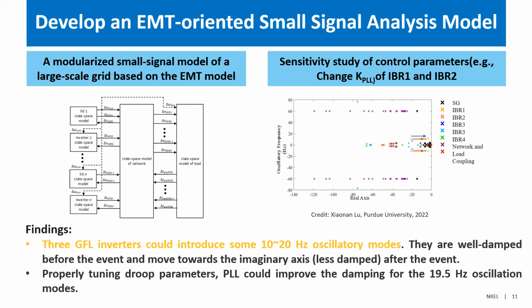We conducted a sensitivity study by changing the control parameters we identified as critical, trying them one by one since this is much faster than EMT simulation. We could clearly see the eigenvalue trace moving from left to right, meaning it becomes less damped, comparing before and after the event.